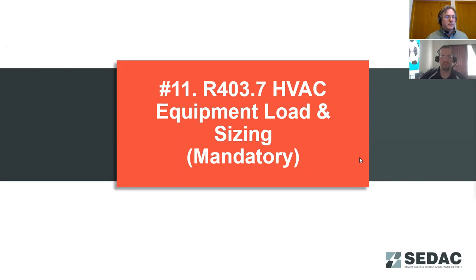Looks like most people have answered the polling questions. We're going to share those results now. Under which condition is duct testing not required? The correct answer is the ducts and air handler have to be within the thermal envelope. I apologize, I did not state that clearly when I went over that slide. But the entire HVAC system has to be within the thermal envelope in order to not require testing for leakage.